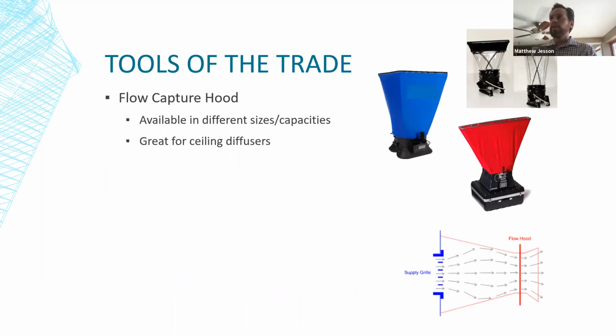And then finally, the tool that most people associate with balancers is the flow capture hood. There are several different manufacturers, and you can get different sizes, different hood tops. So the blue one that you see there is set up for 2x2, and that's really the hood's bread and butter, 2x2 ceiling diffusers. It reads those really, really well. The red one is set up for a linear diffuser. It's just a different top on a similar base.